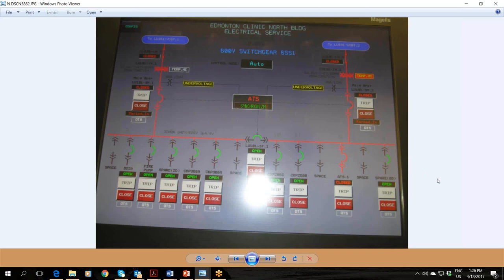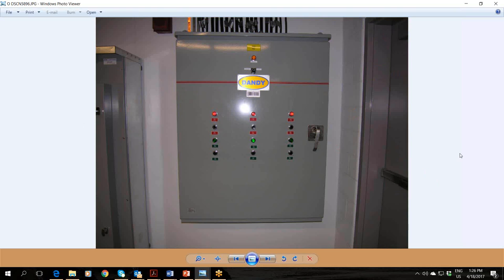Our flavor here is Delta V for distributed control system, which is typically made for industrial plants. So the distributed control is used for the heating plant, for the cooling plant, and electrical is basically tagged on with that for remote control of breakers in the buildings themselves. This is a different screen just showing the low voltage side. So this is a low voltage switchgear, a transformer, the main breaker. As you can see, mains are closed, ties open. That's our normal configuration. And again, you've got control from this HMI screen.